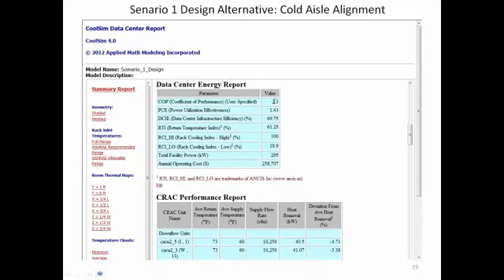18.9% means that there's way too much cold air, and there's an opportunity to push that temperature up now a little bit as a result, to improve the overall efficiency of that heat rejection system. So now if we take a look at our rack inlets, again, they're all conforming now. They're too cold. I mean, they're failing on the cold side, which is still not great from an energy point of view, but at least you're not going to have equipment failure in this kind of case. And we see here that right at the tippy top in a couple of places we're starting to get the racks coming into conformance with the specification.